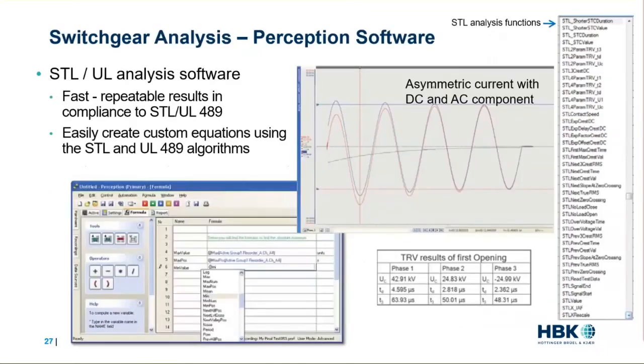Now the software provides complete control, display, and automated analysis and reporting capabilities. The STL analysis option provides fast and repeatable results in compliance to STL and UL 489 standards. In fact, the analysis includes transient recovery results on single or three-phase systems, plus symmetric and asymmetric current. On the right, you'll see a list there of some of the predefined STL and UL analysis functions.